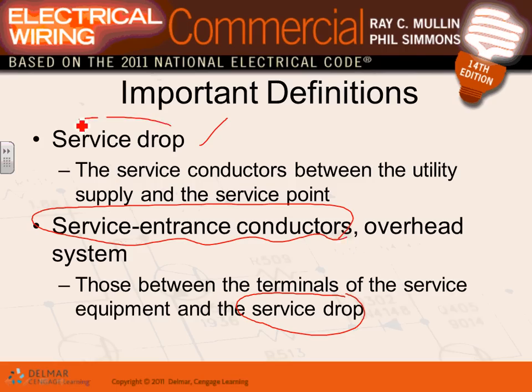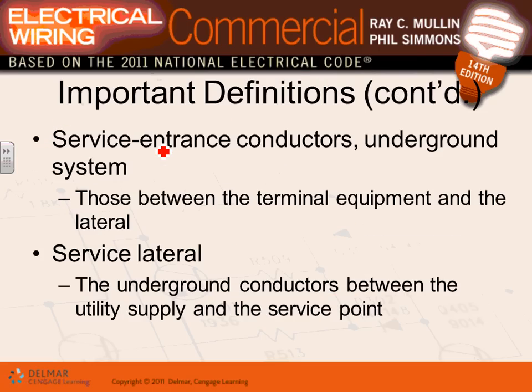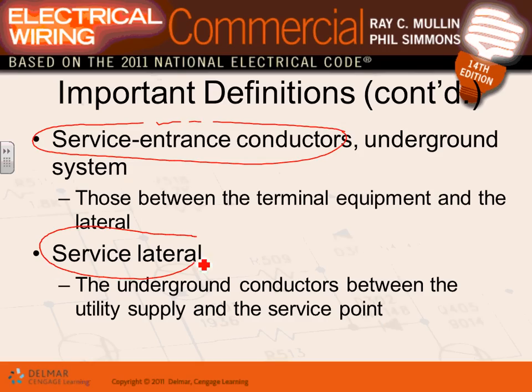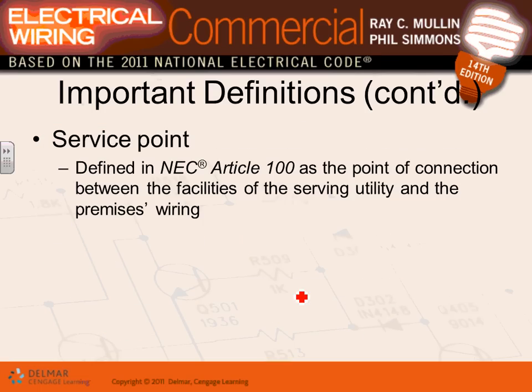Service drop, we have no control over. That's coming from the electrical utilities. Service entrance conductor underground, that's what we also size if we're going underground. Service lateral, that's done by the utility. That's coming from underground between the utility supply and the service point. Utility supply from the transformer to the service point. From the transformer to the service point. Service point, the point of connection between the facility of the service utility and the premises.